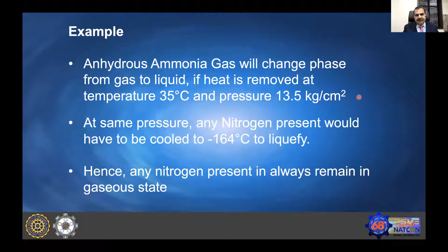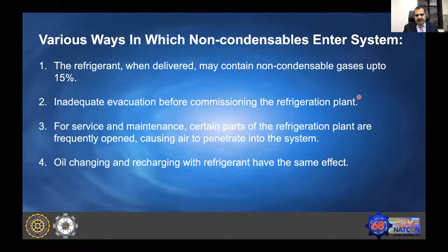How do these gases enter our system? There are various ways by which non-condensable gases or air can enter. One is when we buy or charge the refrigerant, it may not be as pure as required. Secondly, many refrigeration plants are tested with dry air or dry nitrogen, and when doing the evacuation, proper evacuation is not done. Many times vacuum is not maintained to remove the test air or nitrogen used for testing, and it remains in the system. Also, when we open certain parts of the compressor or other parts of the system, air may penetrate. Again, when we are charging or removing oil, it is possible that air may enter the plant from the atmosphere.